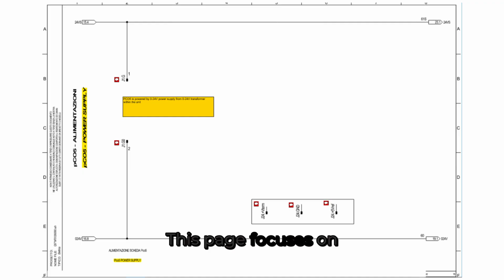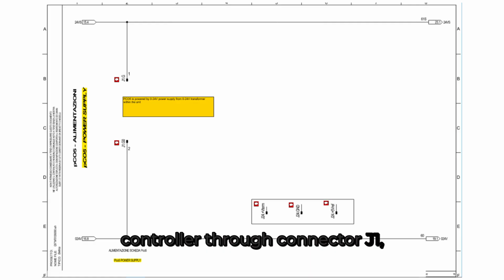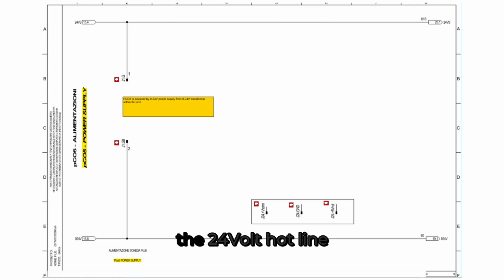This page focuses on the power supply wiring for the Carel PCO5 Plus controller, which serves as the main brain of the air-to-water heat pump from this manufacturer. The wiring enters the controller through connector J1, with terminal G carrying the 24-volt hot line and terminal G0 serving as the neutral or common return. The wire numbers are labeled as 1 and 2, respectively.